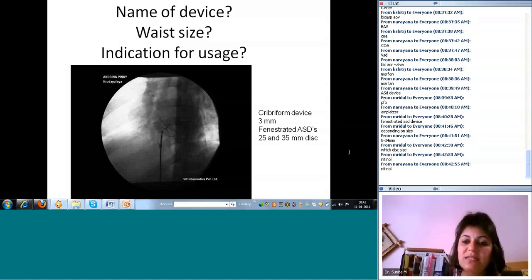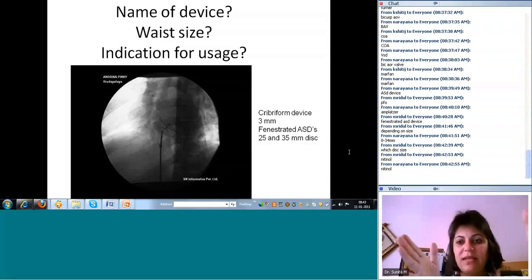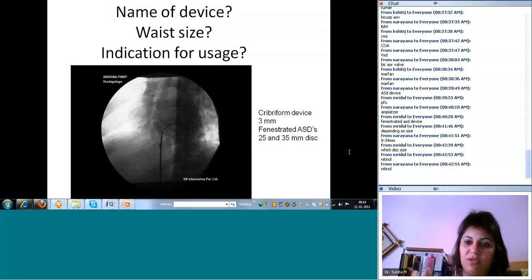And which disc size do you use? That is the question. It depends on two things. One is it depends on the total atrial septum. Let us say your atrial septum measures 27 millimeters. Obviously, you can't use a 35 device. There's not enough space. So then you have to use the 25. If your atrial septum measures 40 millimeters, then you can use either 25 or 35, right?